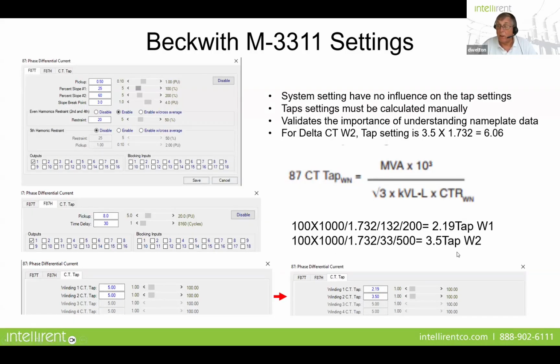You run the same formula for winding 2, and these will be your tap settings. Now, if we go back to the electromechanical days, this is also similar to taking a BD or an HU relay and moving those tap posts into the right position. And what that does is that makes everything equal in terms of what the relay is seeing. Okay, so the tap settings are very important.